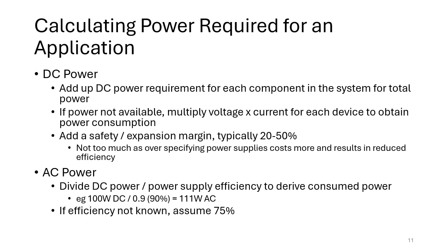So once you know you've got 110 or 111 watts on the incoming supply, you could then translate that into current. So if it was a 110 volt supply, that would be a 1 amp fuse. If it was a 230 volt supply, then it would be about a half amp fuse. And also to take into account the inrush, you might use a miniature circuit breaker, or if it was a fuse, you might choose a slow blow fuse, because there might be an inrush current on that as well. So there are a variety of different ways we can calculate power, but basically it's by understanding the individual power consumption of each device, either as power or current, and then adding all of that up together until we get the final power, and then dividing by the power supply efficiency to get the actual AC input power.